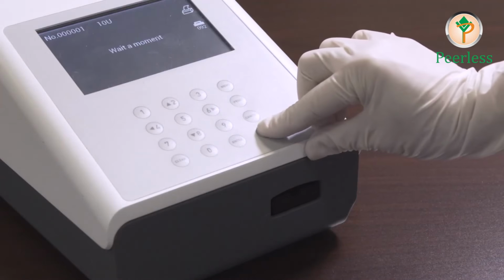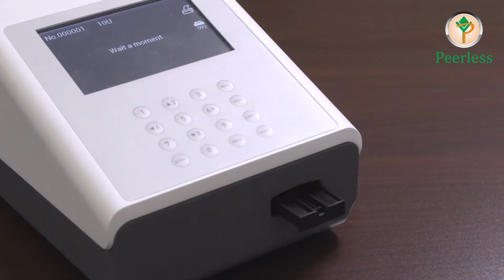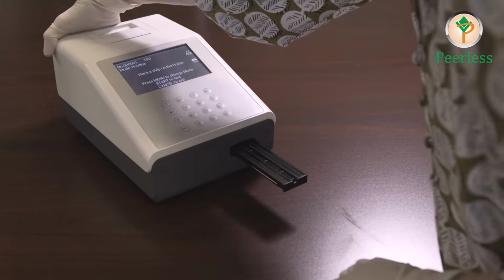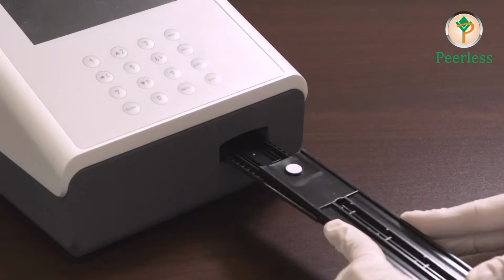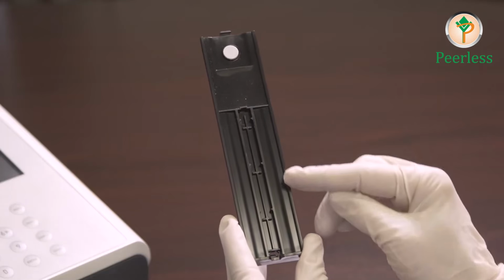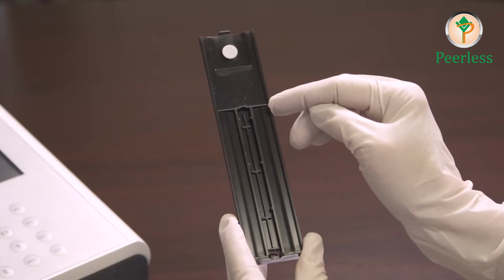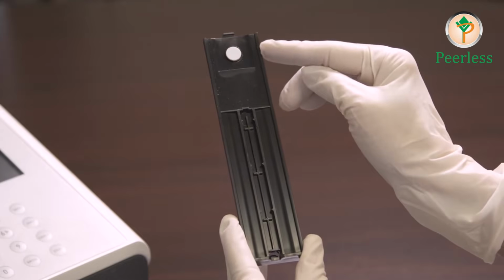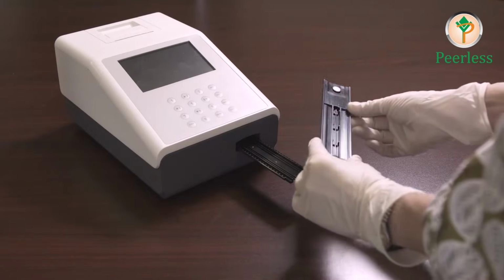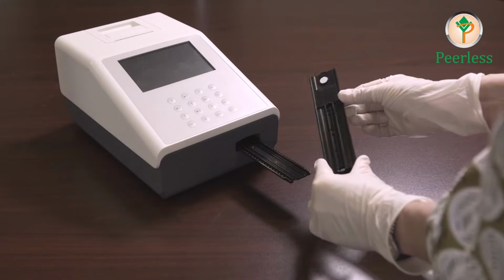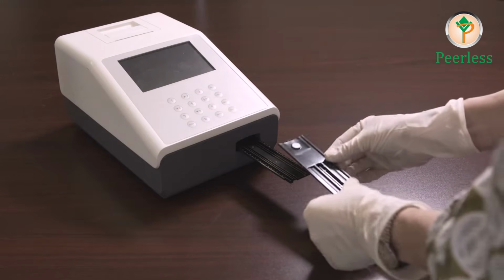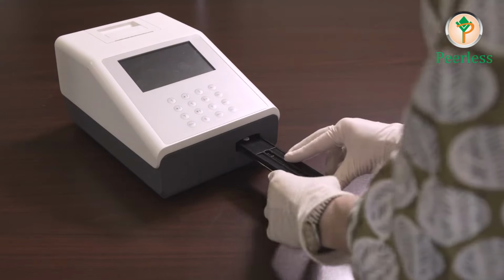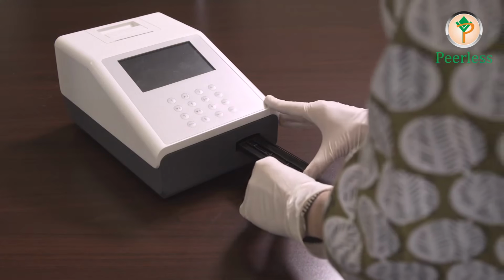For daily cleaning, remove the strip holder by pressing Start to fully extend the strip holder mount. Turn off the power switch after the strip holder mount is fully extended. Then remove the strip holder from its mount by pulling out the sides gently. Clean the strip holder using a lint-free non-absorbent cotton swab ball with distilled water. Be careful and avoid touching the white calibration circle. Then dry with a clean dry cotton ball. Make sure to examine the white calibration circle to ensure that there are no nicks or dirt present.